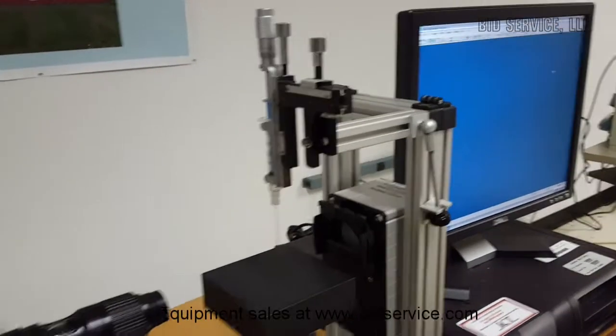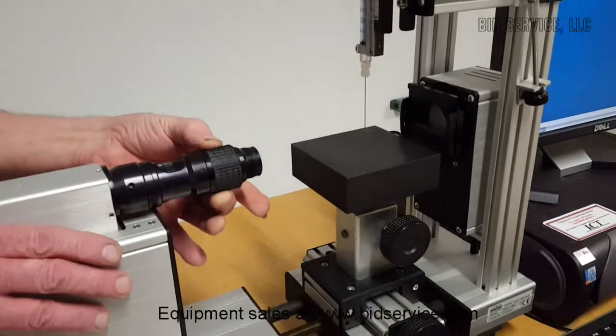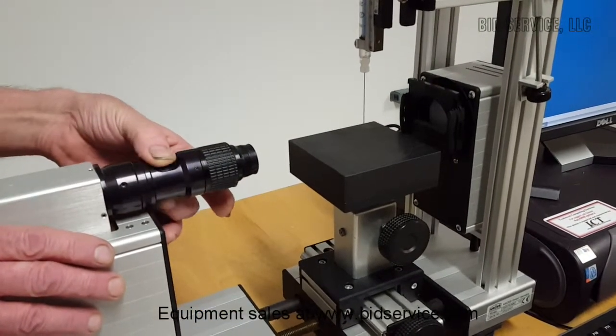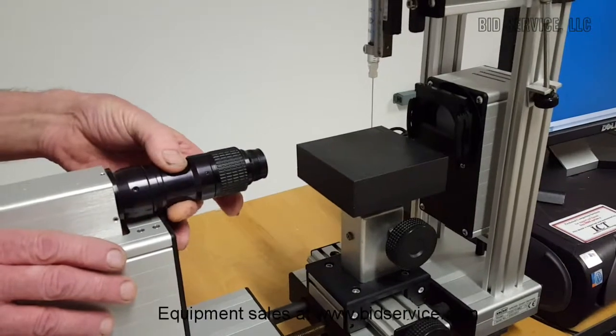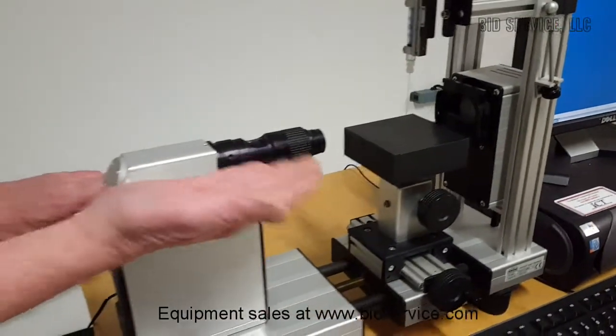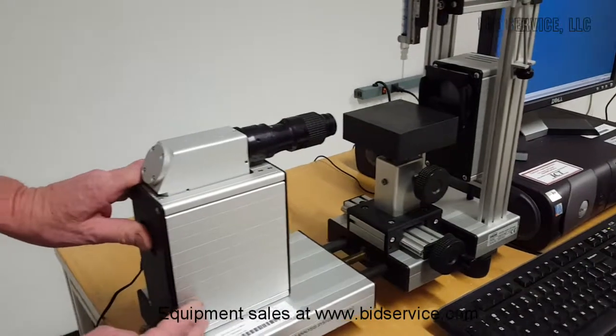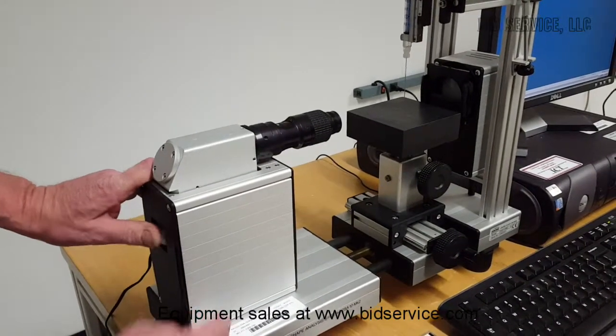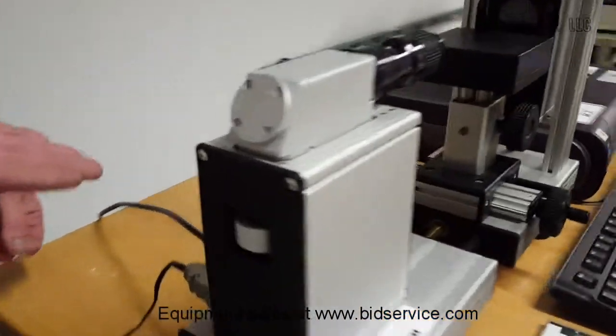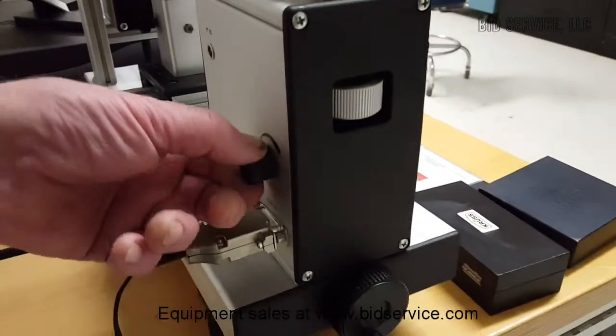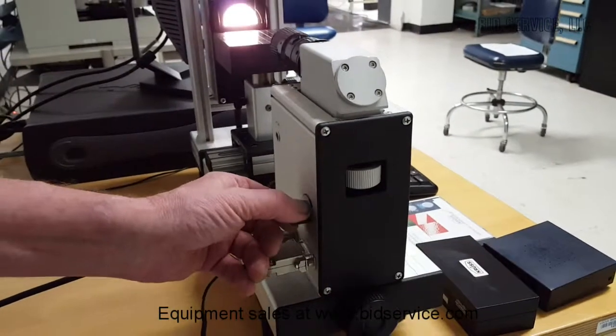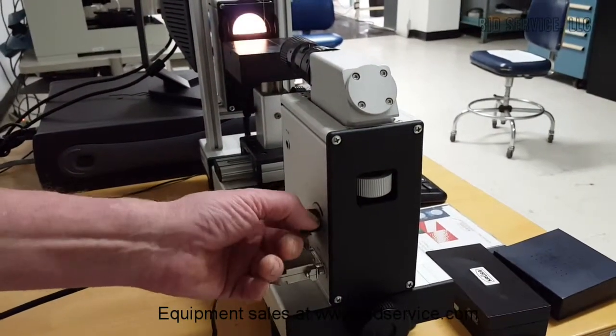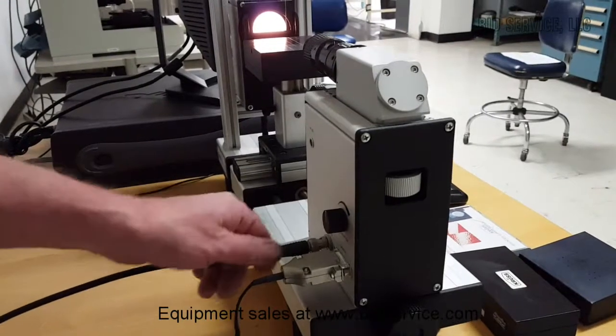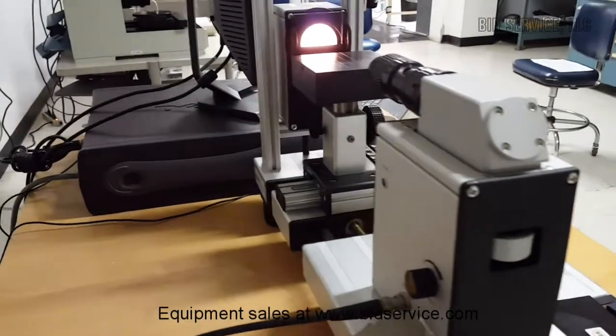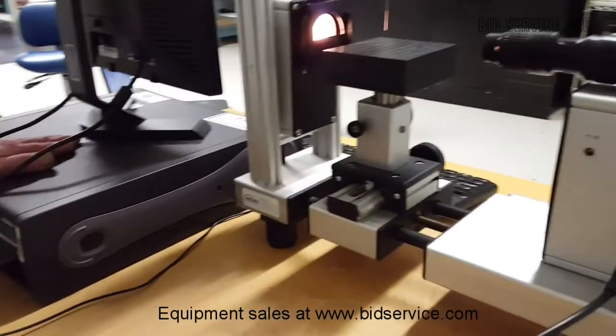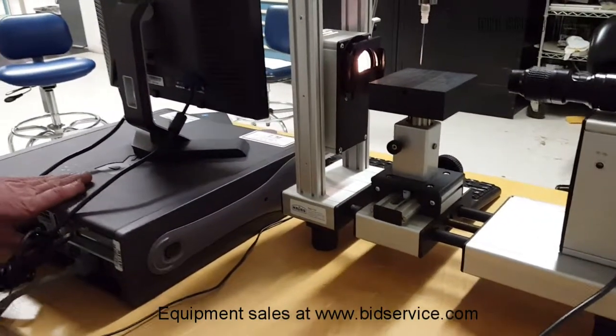On this side, we have the lens, which is a focusing lens here, along with a zoom lens as well. The camera can be tilted up and down using this dial right here. And the adjustment of the light intensity would be behind here, where we have this knob, which will light up our illuminator. This is where we connect our video line out from here. Thus, this one single line goes into the back of our controlling PC, which of course has a frame grabber and will process the video.